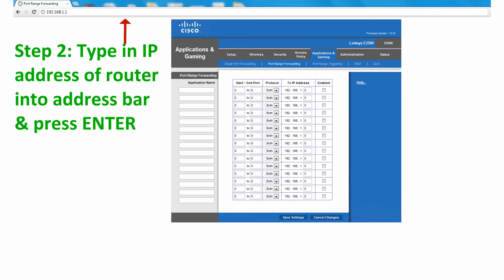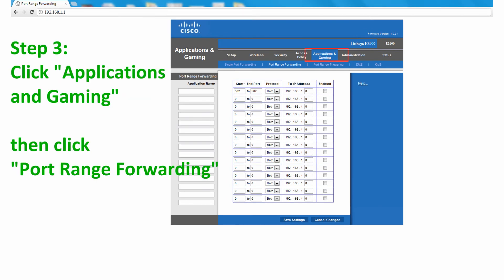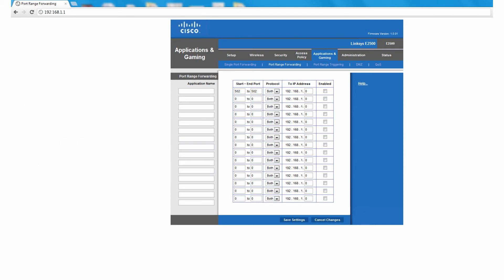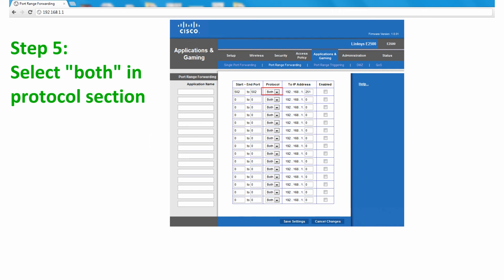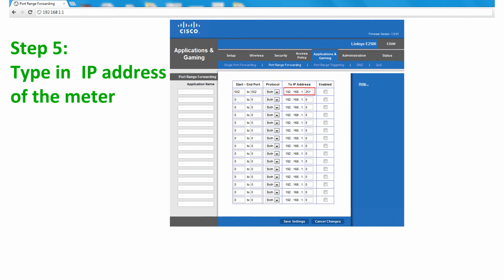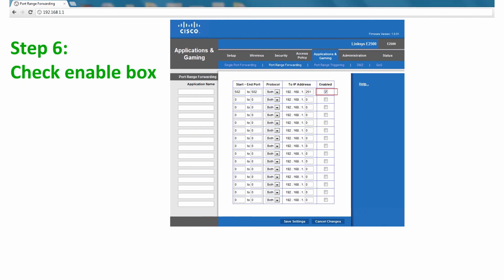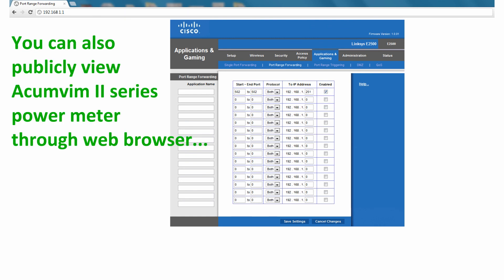We then type in the IP address of the router. Click on Applications and Gaming, then Port Range Forwarding. In this page, you can forward the Modbus port to get external access via our free AccuView software. You need to type the Modbus port number of the meter to start and end the port. In the Protocol section, select both, meaning both TCP and UDP protocols. In the IP address section, type in the corresponding meter address. Check the Enable box to enable port forwarding of the corresponding meter.